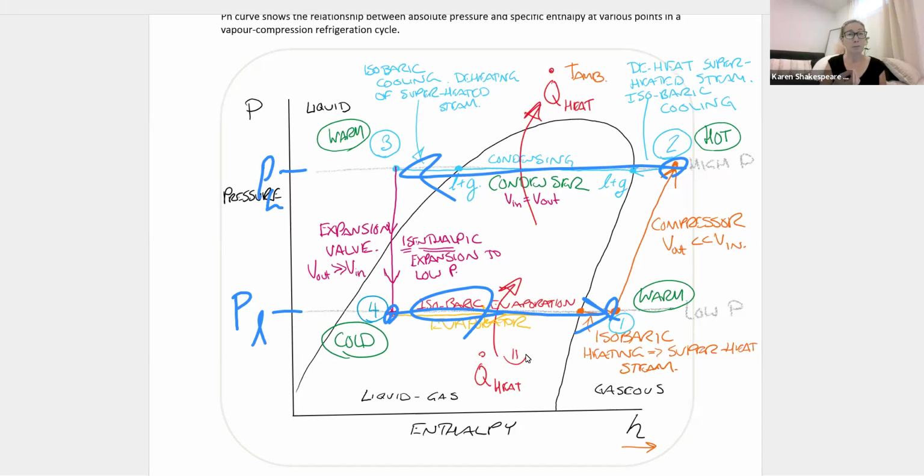So those are a couple of notes of significance, because if you are testing one of these systems, you're going to do your testing at points 4, 1, 2, and 3, and you won't have pressure at every one of them. So you might have 2 of those pressures, and you have to assume that the other one will be along that same pressure line.